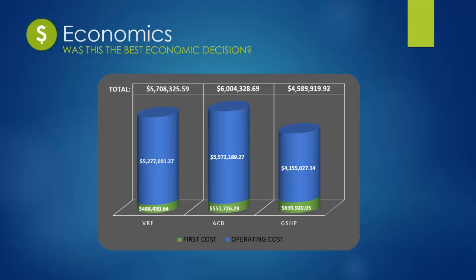The operating cost calculated the present-day value of the utility, maintenance, and repair costs. Ground source heat pump had the lowest operating cost. The variable refrigerant flow system was 27% higher, and the active chilled beam system was 34% higher. Even with the high first cost, ground source heat pump had the lowest life cycle cost.